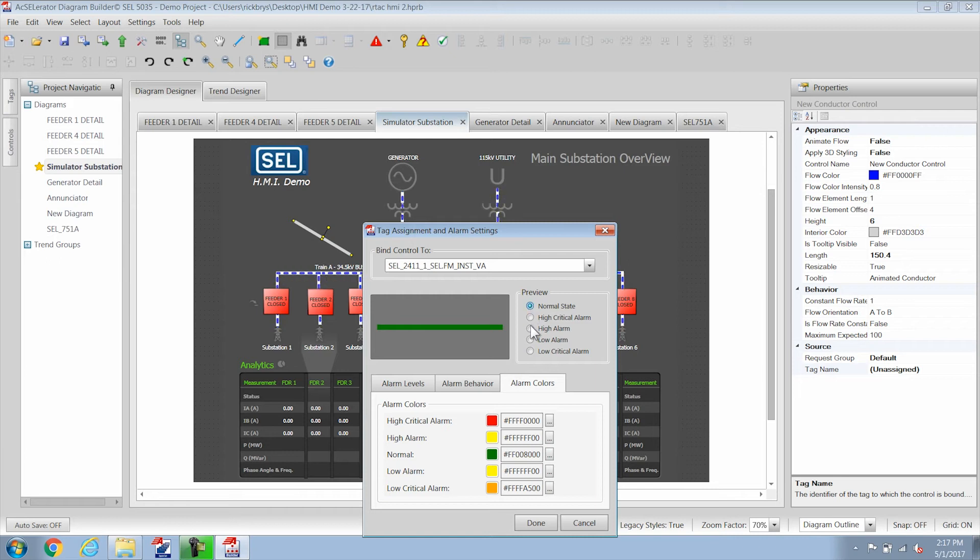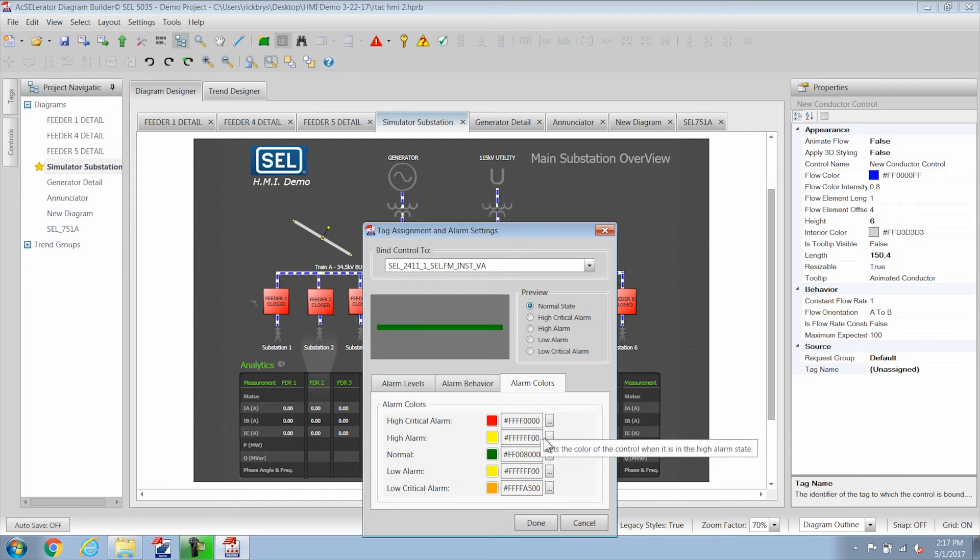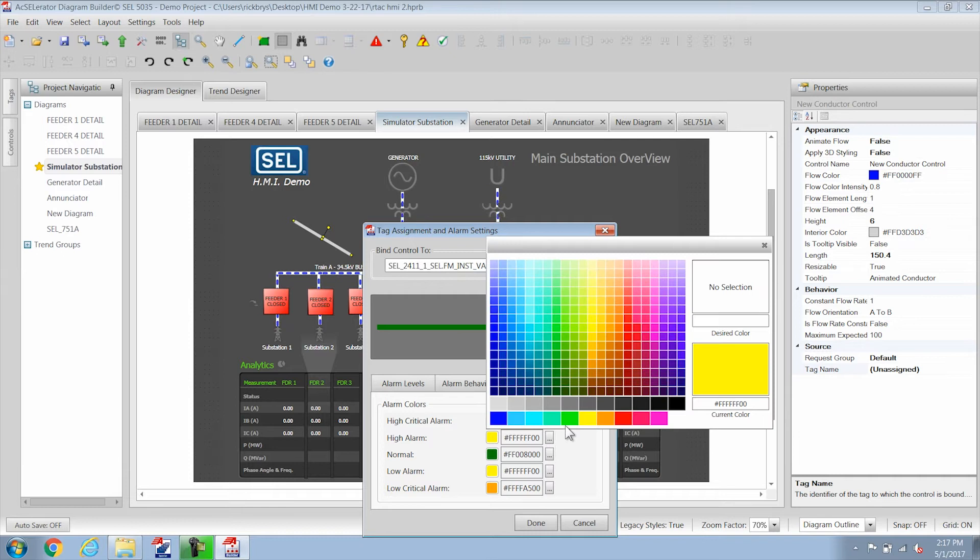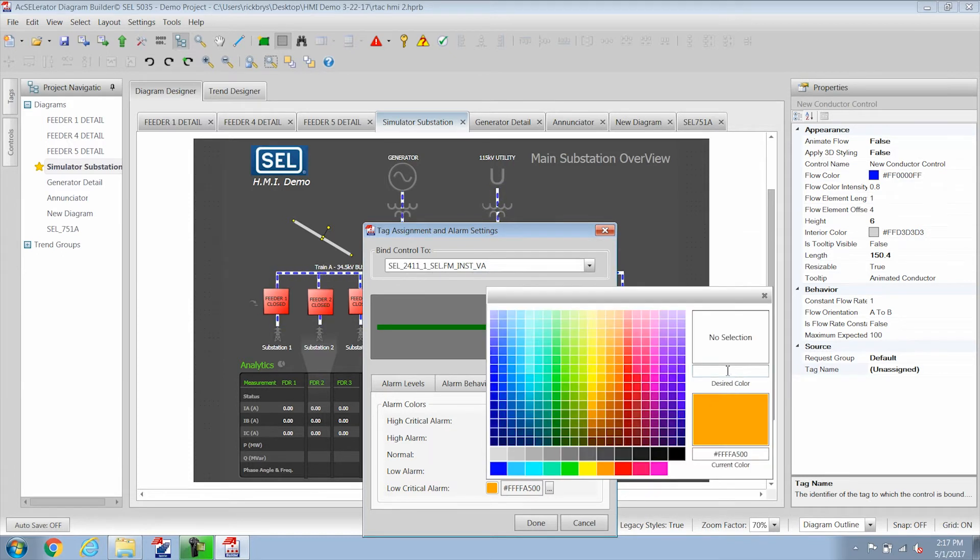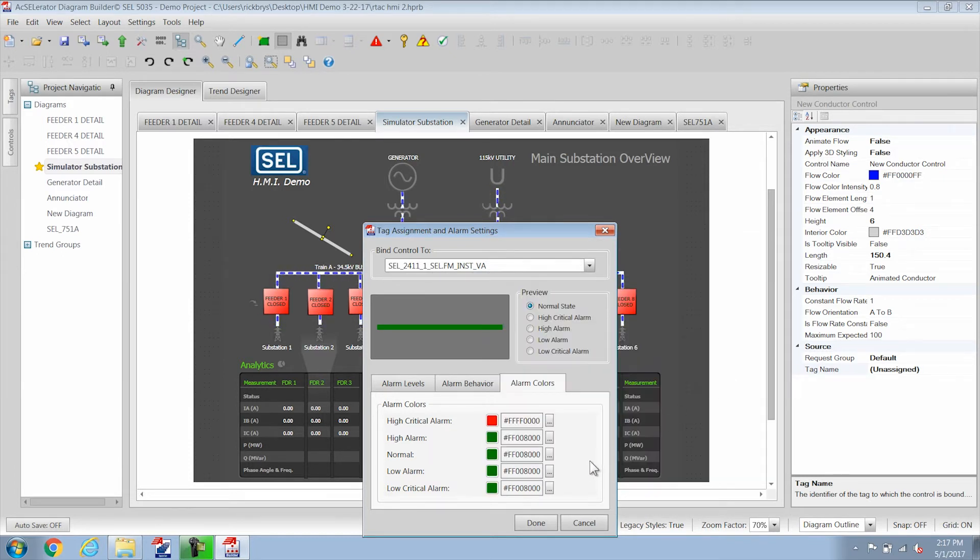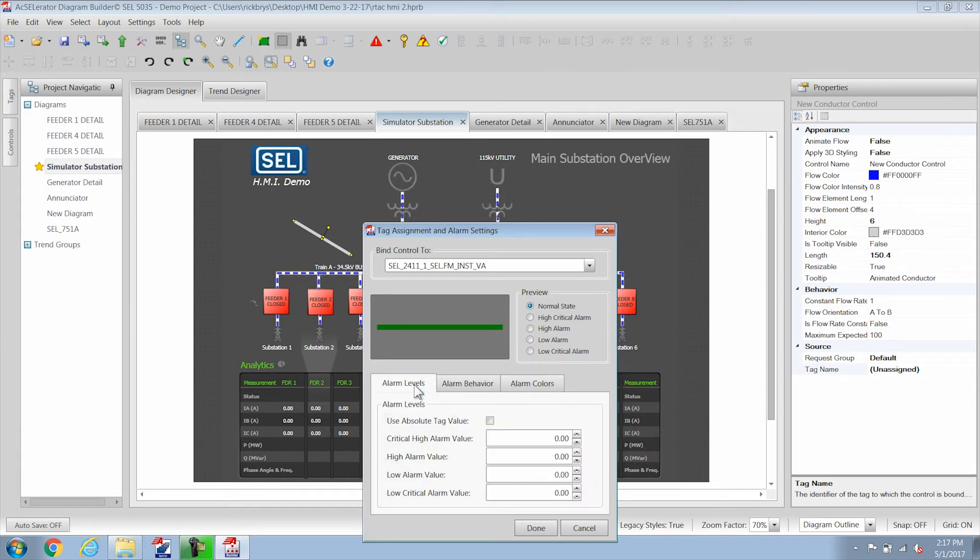So in other words when the alarm goes above a certain value then it will change color. So I'm going to make mine red for the critical high alarm and make it green for the rest of the alarm states. Then change my alarm level to we'll just say 120 volts for the critical high.